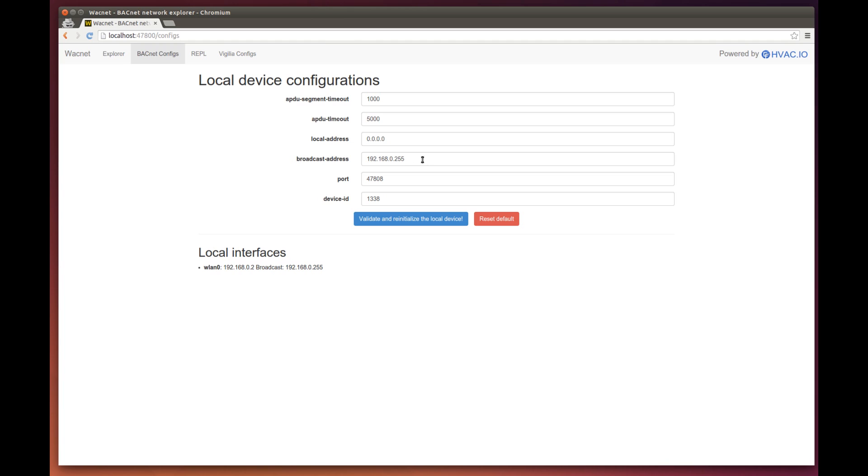The port is the port of your BACnet network. By default, it's 47808.